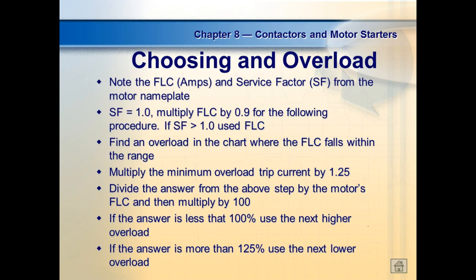What happens is most motors have a service factor. Unfortunately, if I looked up the service factor on our motor over there, y'all can go look at it. It says SF, and it's going to say one. Which means I cannot overload that motor. It's a one and a half horsepower motor, right? That's the exception to the rule. Just about all your industrial motors have the ability to overload. So when I set up my chart for my heaters, I'm going to assume it has a service factor of greater than one.